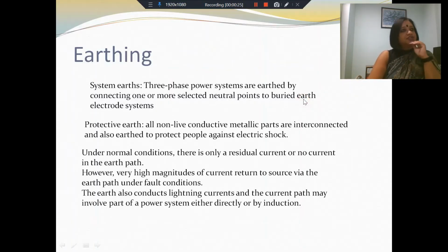The first definition is that of a system earth. Now, whenever you have a three-phase power system, it has to be earthed. And generally, this earthing is done by connecting at least one neutral. You can select more than one neutral point, and you connect the neutral points to a buried earth electrode system. So this is one aspect, that every system has a system earth.